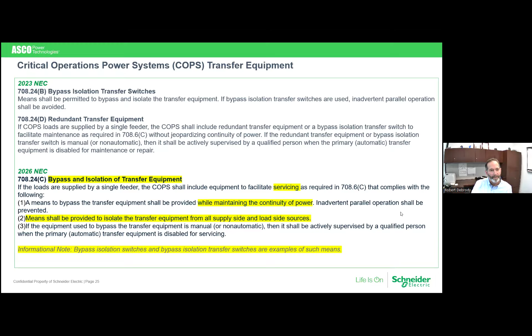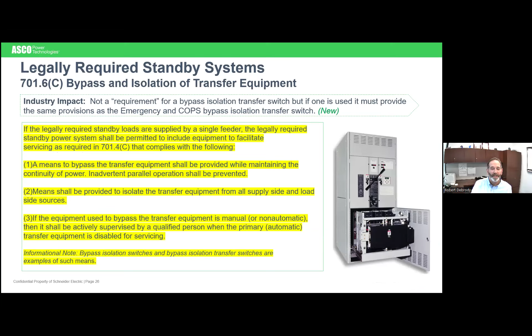And this is what happened in legally required standby systems. They're not requiring the bypass isolation transfer switch, but they're permitting the use of it. And the funny thing is, let's look at what it said before. So this is the paragraph in 2023. It says, means to bypass isolate a transfer switch shall be permitted. Well, okay, they're just giving you permission to use a bypass switch. But now, with the change that they made in 2026, they're saying, okay, if your legally required standby loads are supplied by a single feeder, you can use a bypass switch. Okay, and this is how you do it safely. I think that's really what they were trying to do. They're trying to make sure that you're going to do it safely. So they're providing some guidelines in here on how you do that.